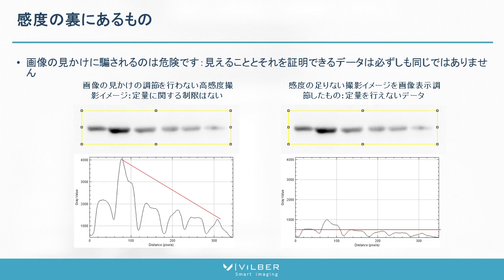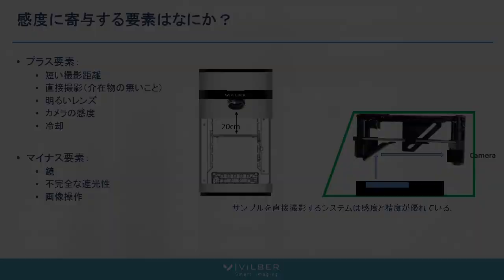When you have an image, you have to be very careful, because we are always able to optimize the display of the image so that you can see your proteins nicely. However, when you look at the profile — the quantitative data from the protein volumes — you can see that in one case we have a large quantity of data and we have information, while in another case we have a very weak signal but the display has been optimized. We feel comfortable with the image, but we should not — because looking at the profile shows we cannot get any useful data from this image. We don't have linearity and we cannot reach the limit of quantification.